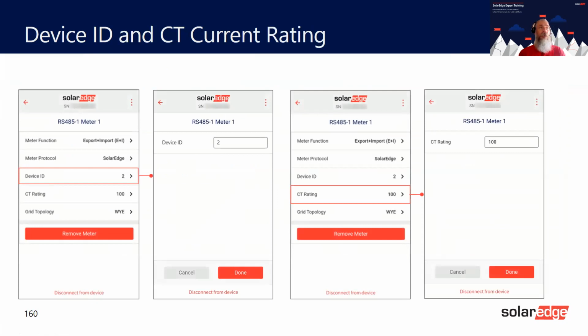And then just to show you again, device ID 2. You can see it's the number 2 on here, even though it's meter 1, we've changed that. The CT rating goes to 100. It automatically populates itself as long as everything is right. If you can't select the CT rating, no matter what you do, it's because you either got a cable loose or the CT is not clipped or clamped around the cable correctly. And this will never populate unless that's correct. So if you've done the CT correct, you've done the cabling correct, this will automatically appear.